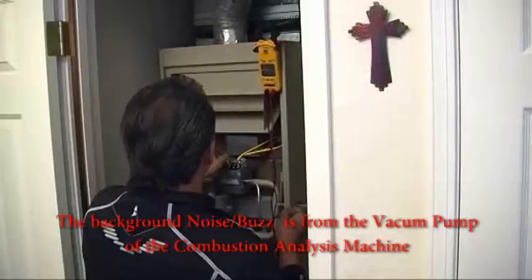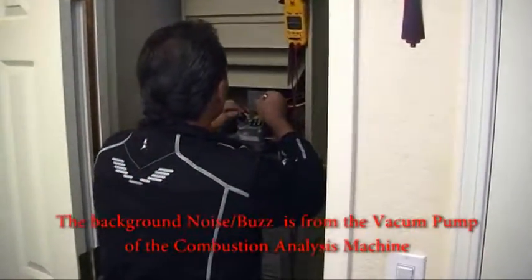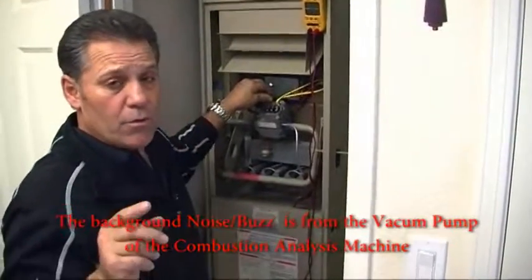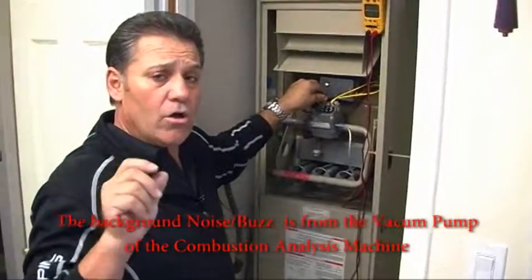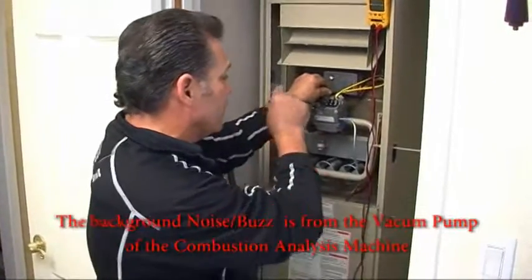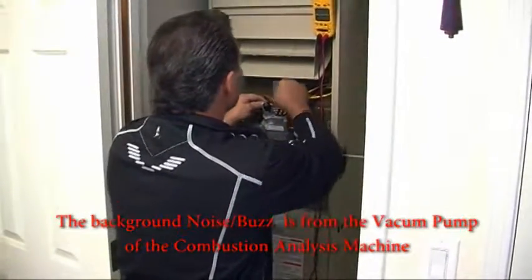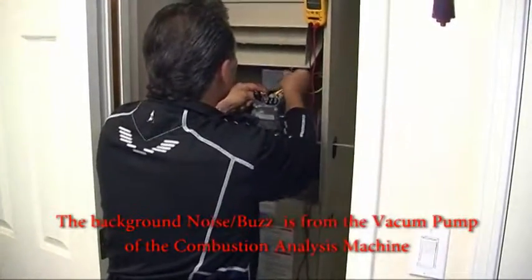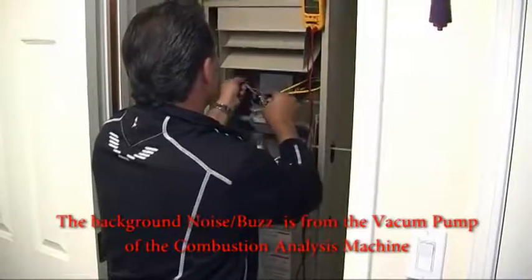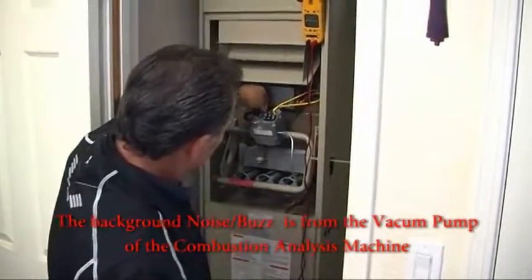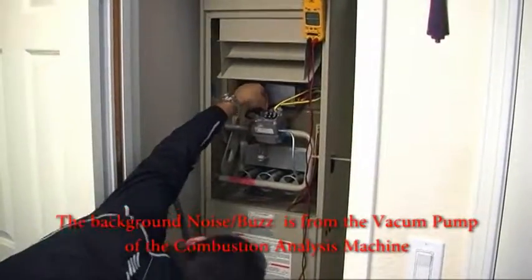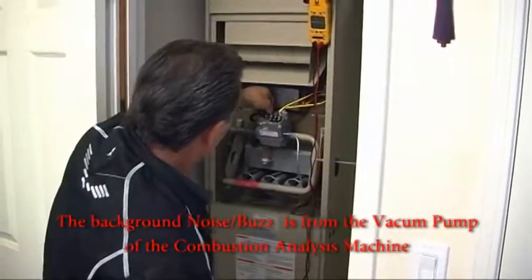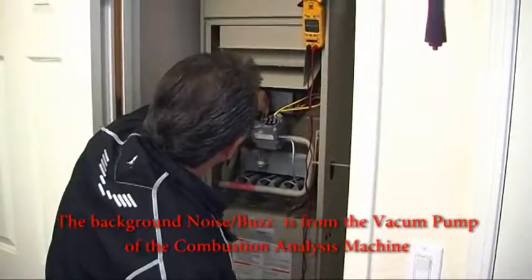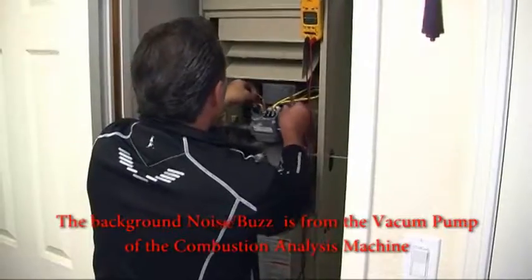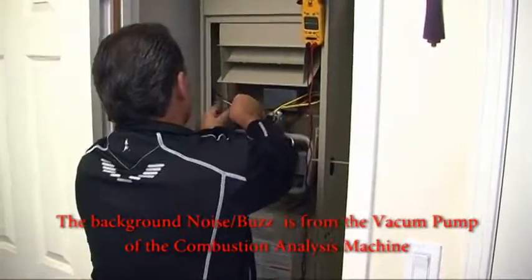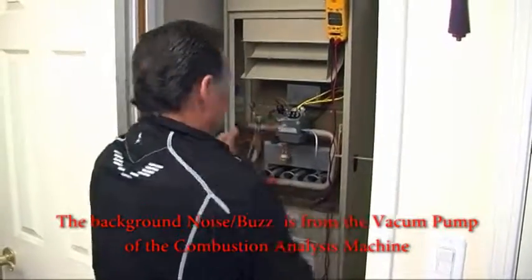So let me move into turning the furnace to the off position. So we're shut down, and I'm going to remove the thermocouple. Now, all you need to do is hand tighten it a quarter turn. So I should not have to move this very much at all before I use my fingers to loosen it the rest of the way, okay? So there we are, and then I'll be able to remove this from here. Pilot's out. And my thermocouple's out.